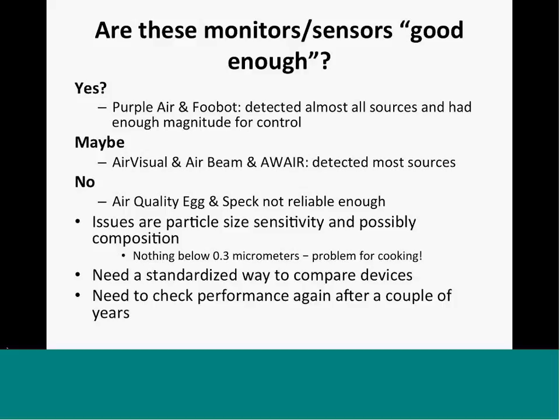And the last thing here is that we tested these things and they were all brand new, out of the box, and we don't know how well they're going to work a few years down the road. There's certainly a possibility of things building up inside the sensors themselves, electronic drift of components and so on, that may change some of these results. And that's something that we really need to look at in the future, is possibly doing some accelerated testing or keeping these sensors activated and redo these tests in a couple of years.